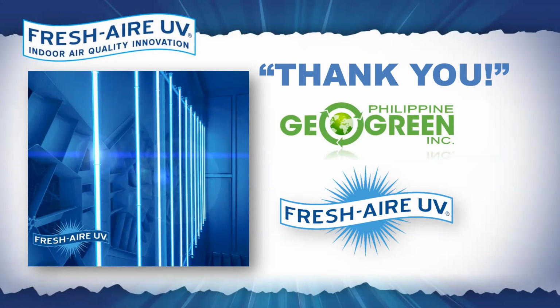So we could produce ozone if we wanted to—it's a frequency of a lamp, and we do have ozone lamps. We use them for exhaust-to-outside applications. For example, with wastewater treatment, if there are noxious odors being exhausted outside the building, we'd put high output ozone lamps in the exhaust ductwork. We're not concerned about occupant well-being there because it's an exhaust duct. But we will not put ozone lamps inside ductwork that recirculates air back into the building.